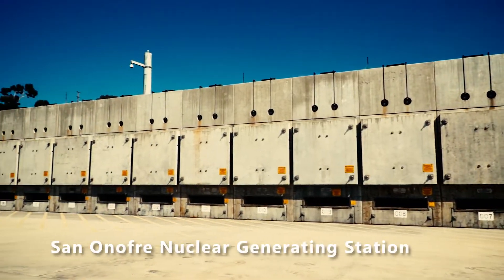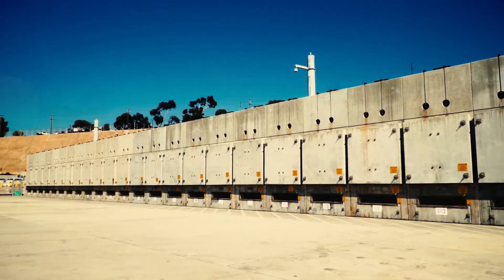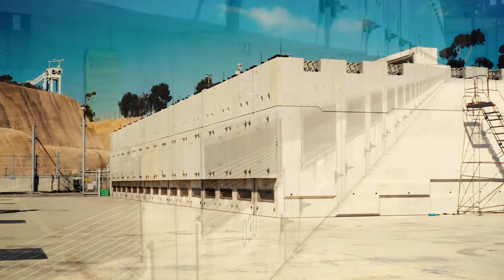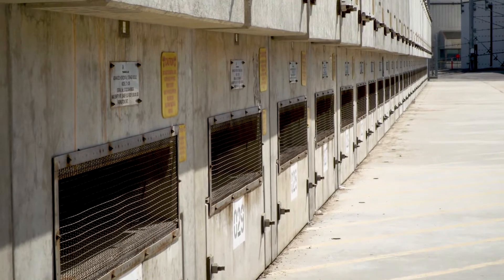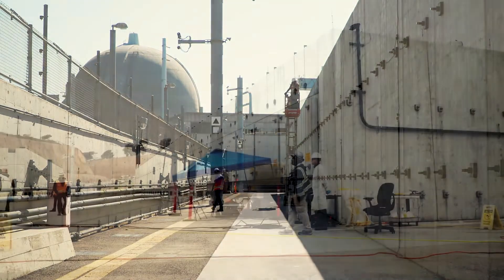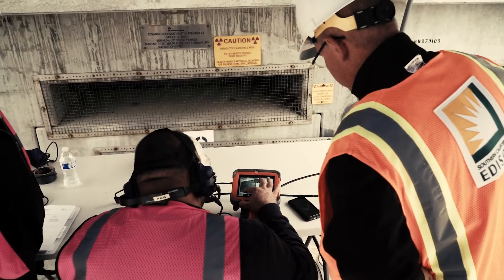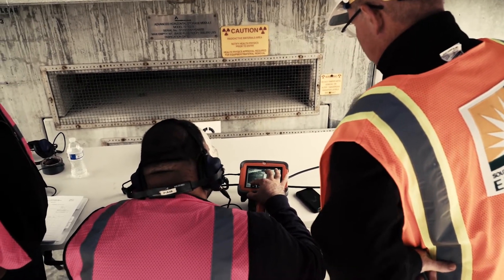The TN NUHOMS Dry Fuel Storage System at San Onofre holds 50 canisters of spent nuclear fuel. Dry fuel storage systems in the U.S. are initially granted a 20-year license by the Nuclear Regulatory Commission. SCE loaded the first canister into the NUHOMS system in 2003, meaning its first 20-year license will expire in 2023. As part of relicensing the system, baseline inspections are performed that will help guide future inspections during the next licensing period of the system, which is 40 years.